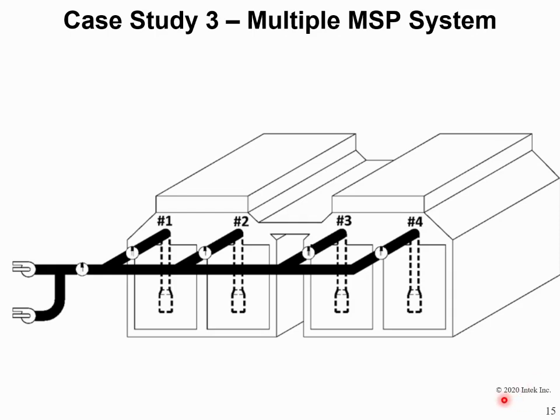This last case study is an Ingersoll Rand condenser. There are two condenser shells running at a common pressure. Each shell has two bundles, each with a dedicated air offtake line. This unit operates with three RheoVac probes.